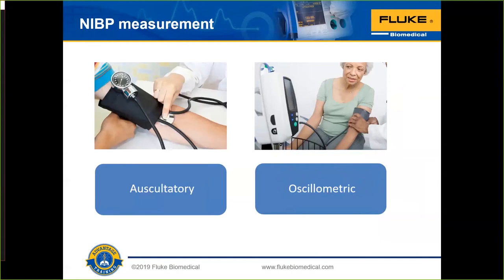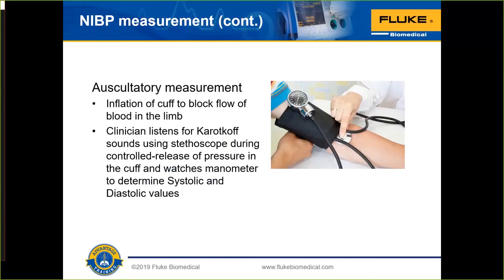There are two general ways we determine non-invasive blood pressure. The first is auscultatory — the way nurses and doctors have been taught in school. When you go to the doctor's office, they take a blood pressure measurement this way, auscultatory. Or, increasingly nowadays, they use an automated blood pressure device, which is an oscillometric device. In auscultatory measurement, we inflate the cuff until we block the flow of blood in the limb where we're listening to the blood vessel.